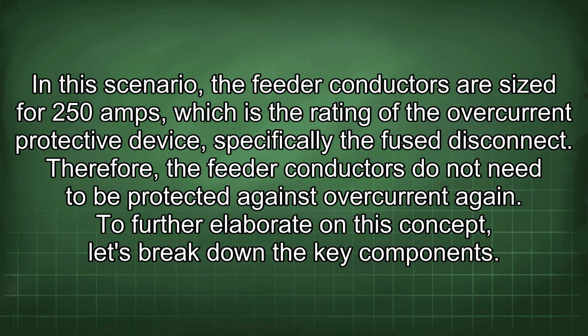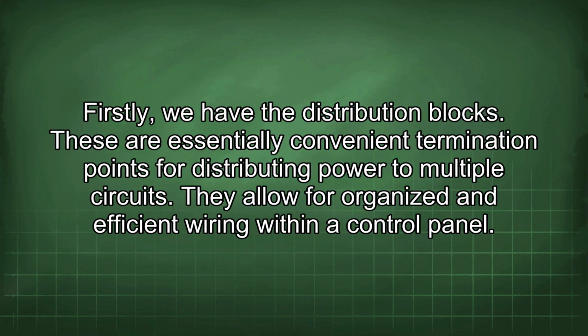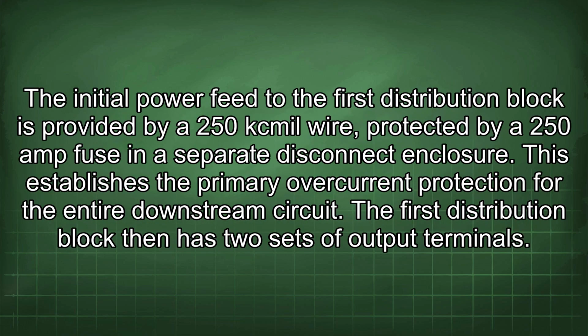To further elaborate on this concept, let's break down the key components. Firstly, we have the distribution blocks. These are essentially convenient termination points for distributing power to multiple circuits. They allow for organized and efficient wiring within a control panel. The initial power feed to the first distribution block is provided by a 250 kcmil wire, protected by a 250 amp fuse in a separate disconnect enclosure. This establishes the primary overcurrent protection for the entire downstream circuit.